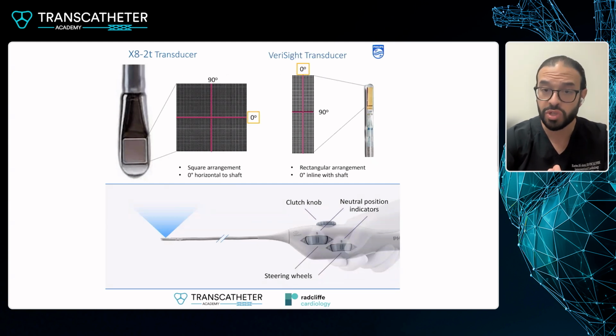The ability to image in a rectangular arrangement is different from a square arrangement. And so at a 90-degree angle on an ICE catheter, the images may be somewhat limited. And so a lot of times we will be utilizing 45-degree angles in order to utilize the diagonal imaging elements on the ICE catheter as compared to TEE.